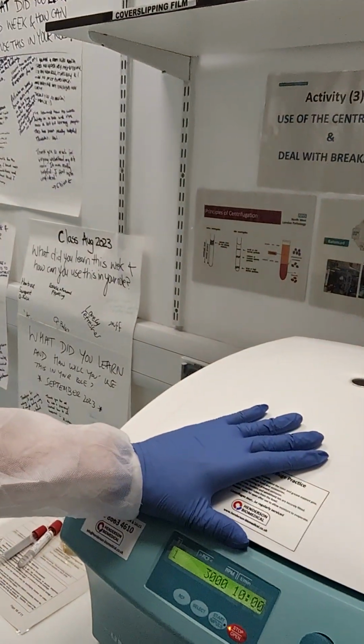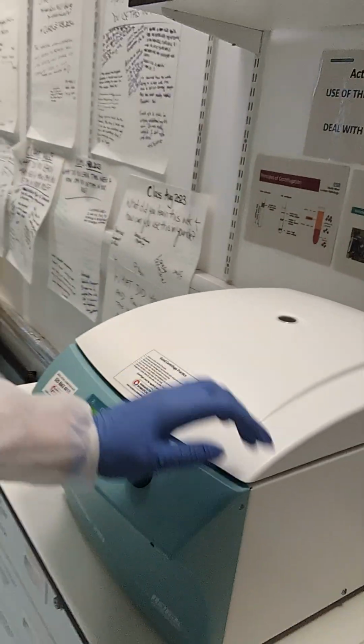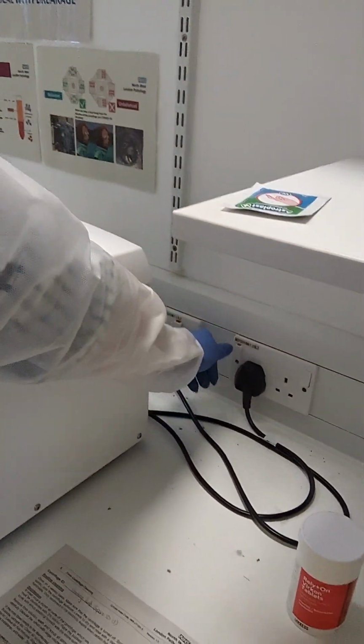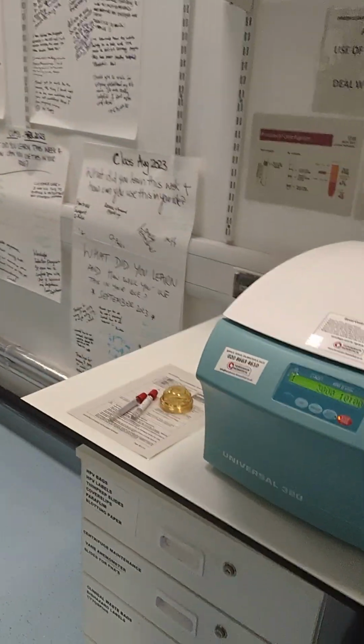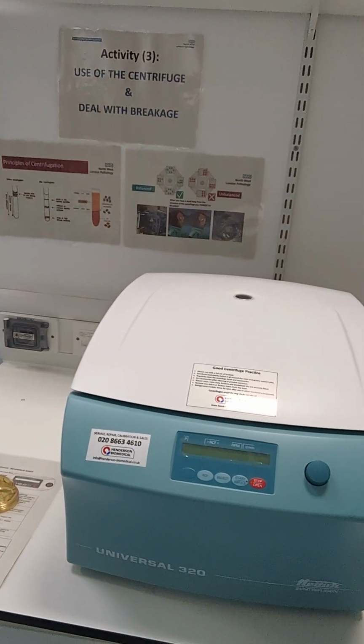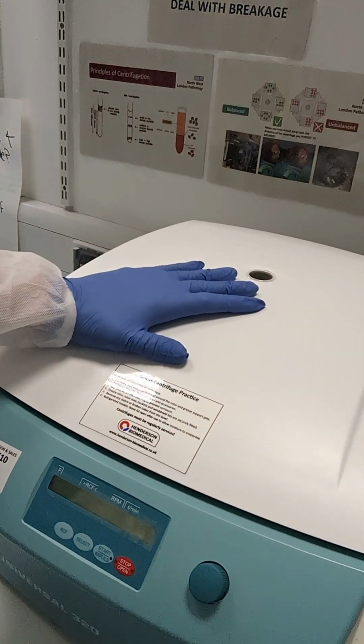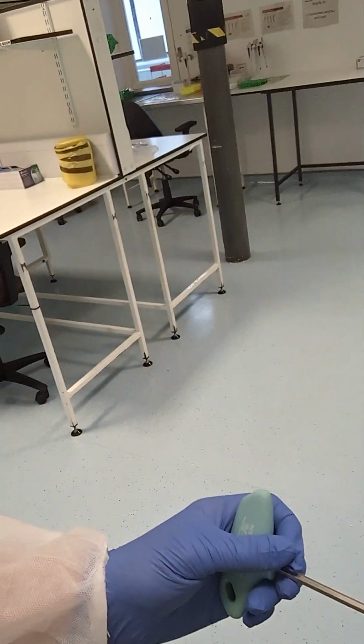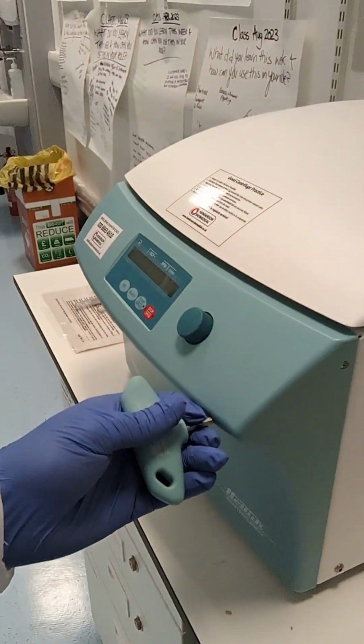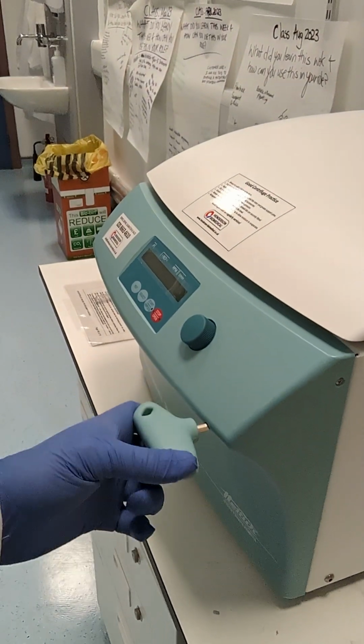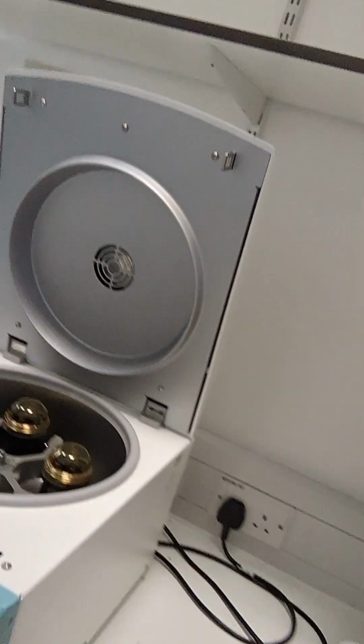I can't open the lid for some reason, it seems to be stuck. Just to make sure though, I will turn the power off. And I will leave the centrifuge for 10 minutes to make sure that if it was actually running, it will have stopped. You can also put your hand on it and make sure it's not vibrating and not in operation. So I've made a decision, it's now safe, the centrifuge is definitely not spinning, and I want to open the lid. With the power off, I can take the key. There will be a little hole in the front of the centrifuge. You insert the key, you turn, and the lid will open.